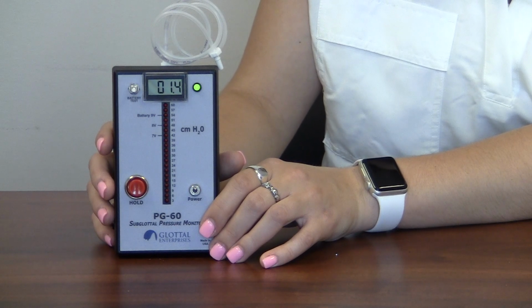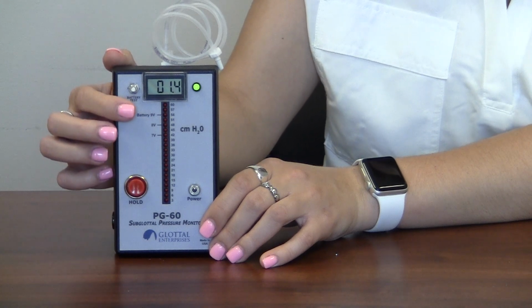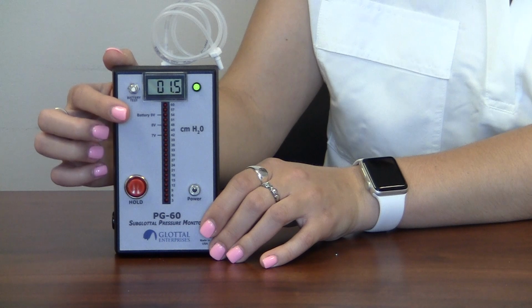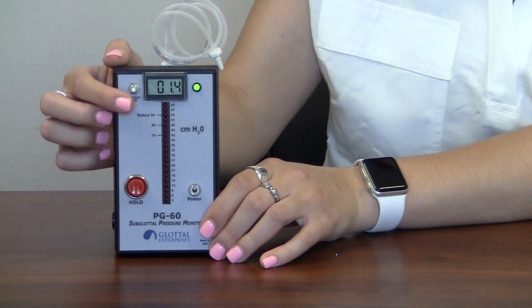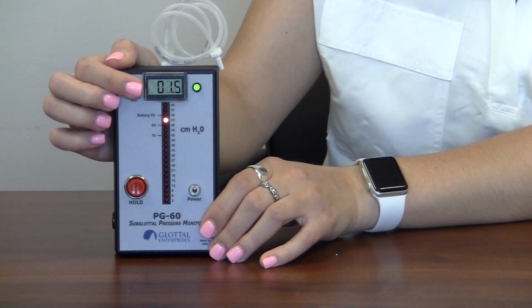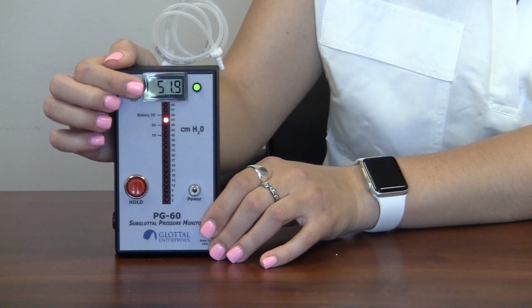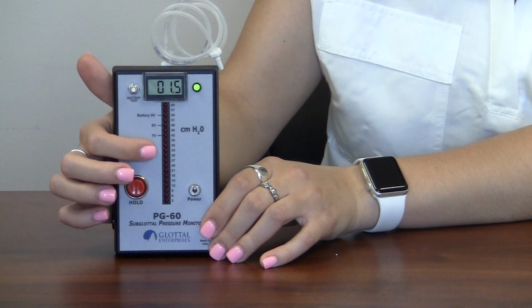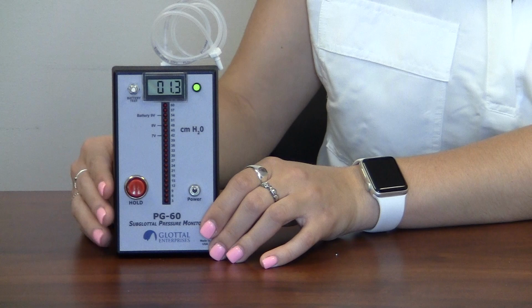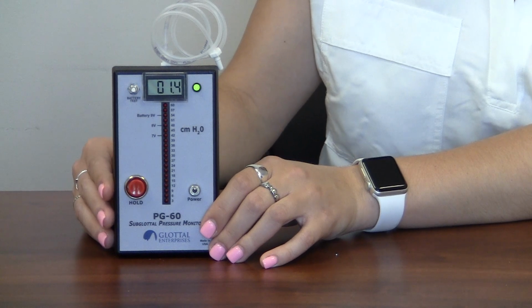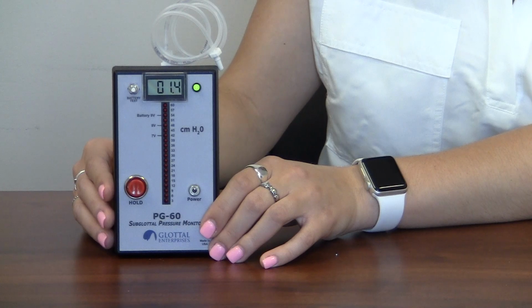The battery condition can be checked by pressing the battery test button on the front panel. The unit must be operating when you do this. During this measurement, the red LED light on the linear display will read the battery voltage. The voltage markings on the left side indicate the battery strength. A voltage greater than approximately 7 volts indicates that the battery can operate the unit correctly.